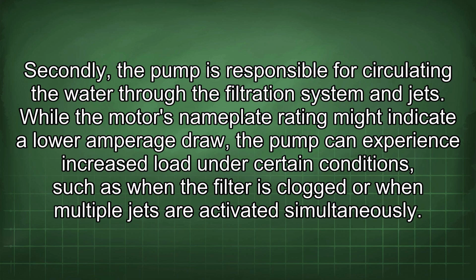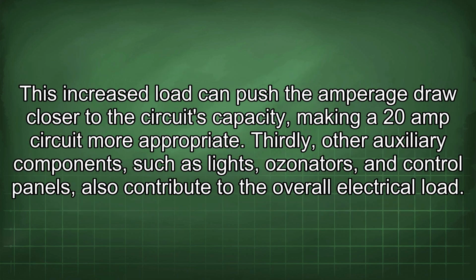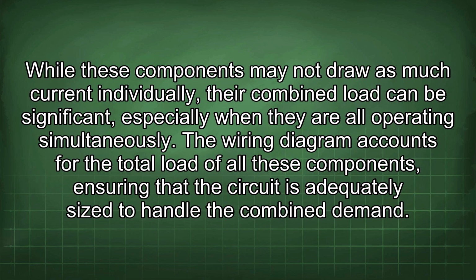Secondly, the pump is responsible for circulating the water through the filtration system and jets. While the motor's nameplate rating might indicate a lower amperage draw, the pump can experience increased load under certain conditions, such as when the filter is clogged or when multiple jets are activated simultaneously. This increased load can push the amperage draw closer to the circuit's capacity, making a 20 amp circuit more appropriate. Thirdly, other auxiliary components such as lights, ozonators, and control panels also contribute to the overall electrical load. While these components may not draw as much current individually, their combined load can be significant, especially when they are all operating simultaneously. The wiring diagram accounts for the total load of all these components, ensuring that the circuit is adequately sized to handle the combined demand.